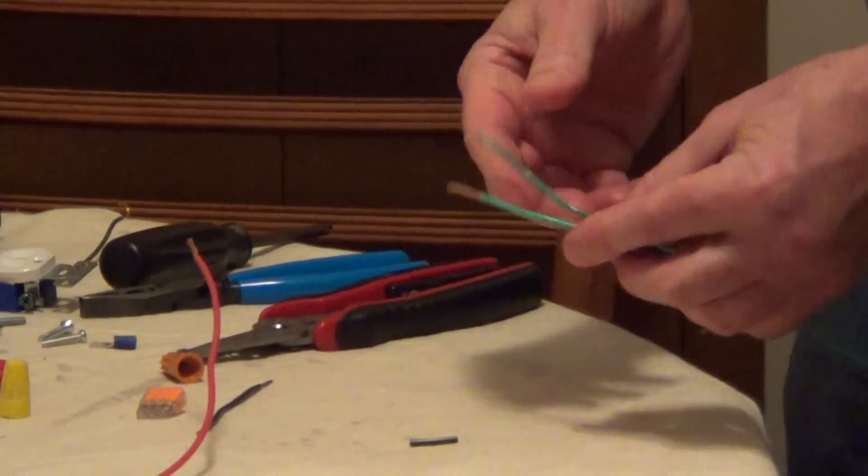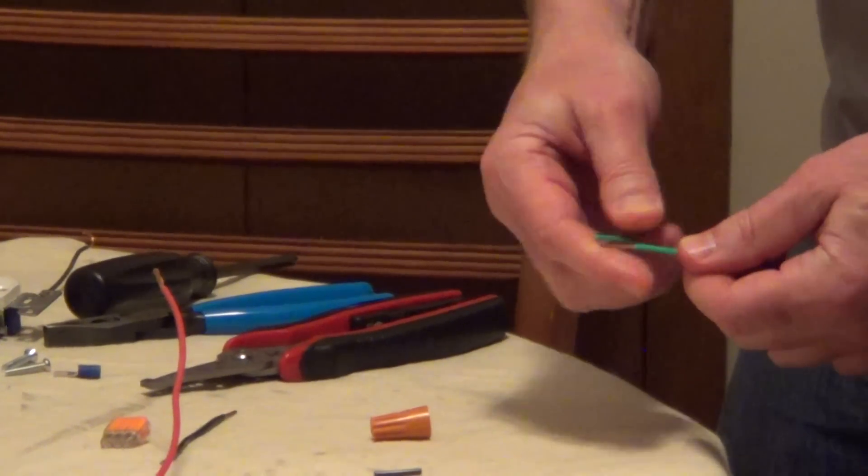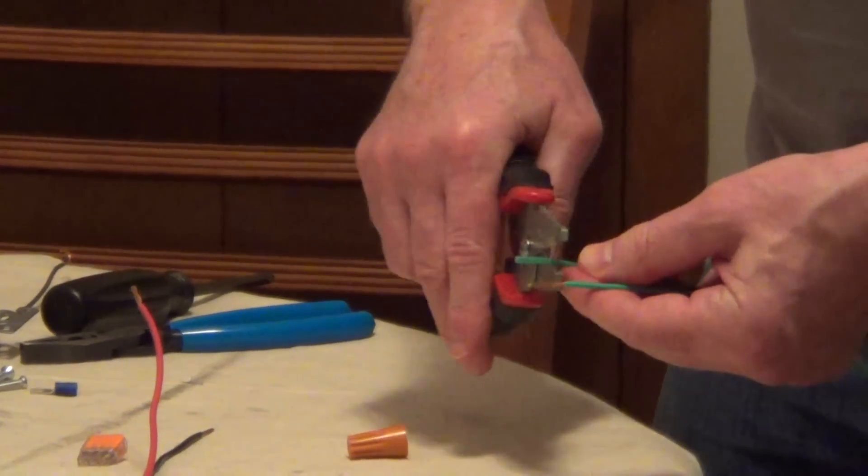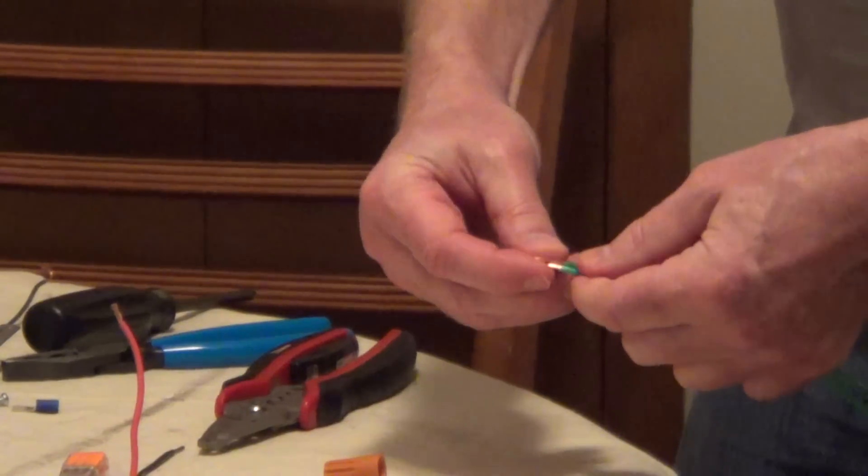Now, if you're connecting two wires or three wires together underneath a wire connector, you would only want to strip about a half an inch to five-eighths of an inch so that this exposed wire stays underneath the wire connector.